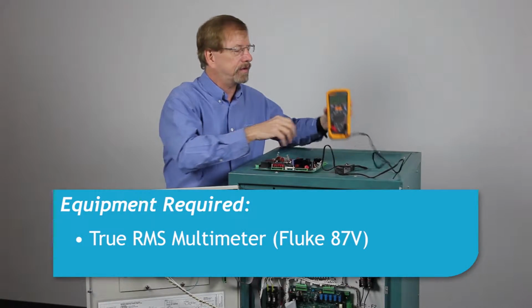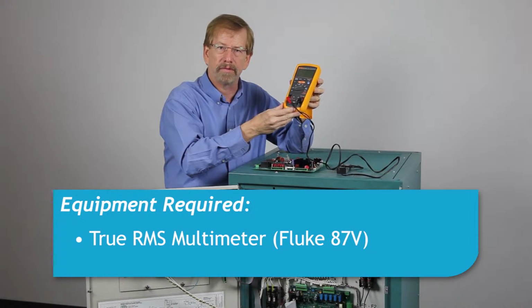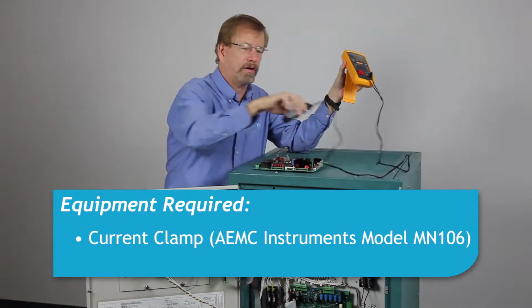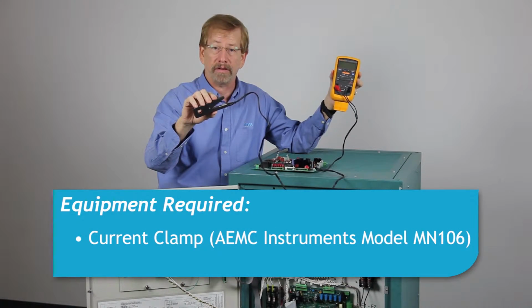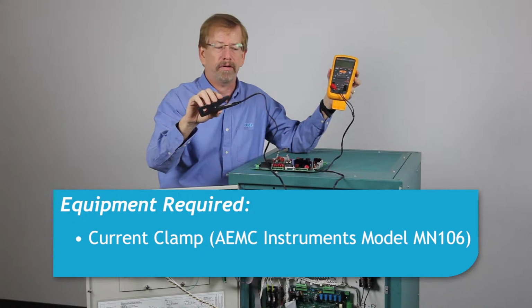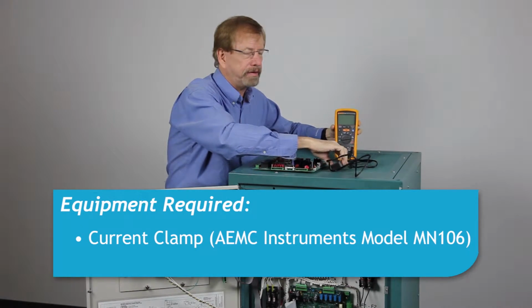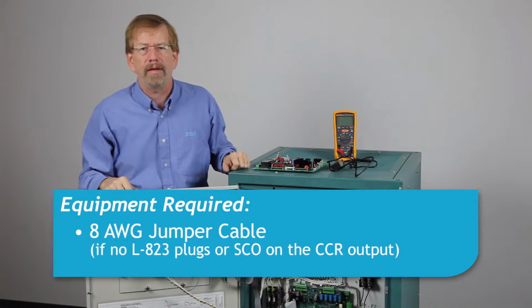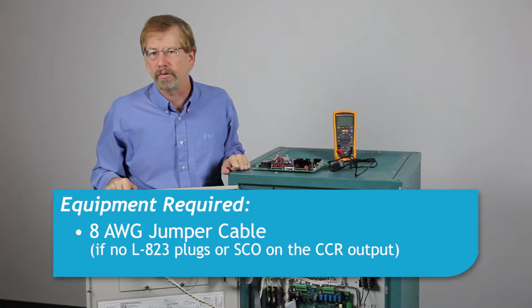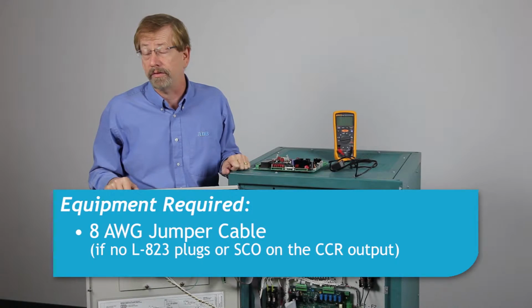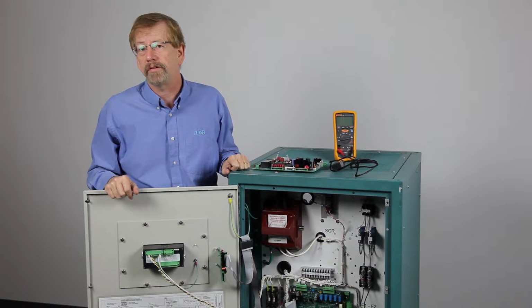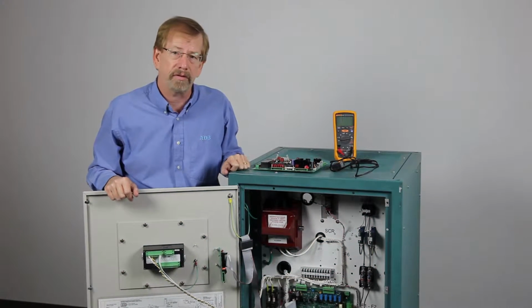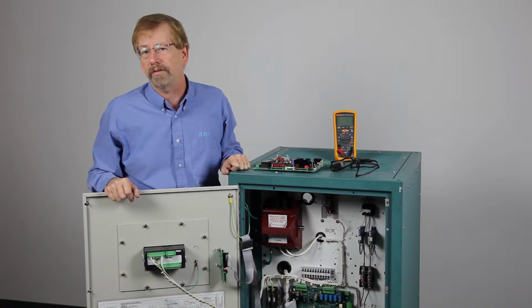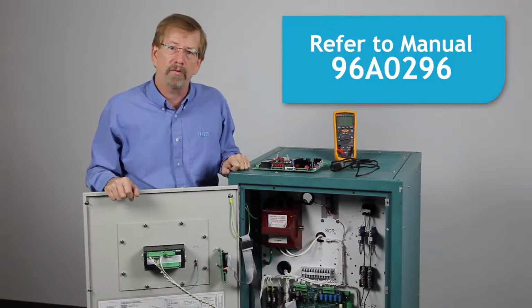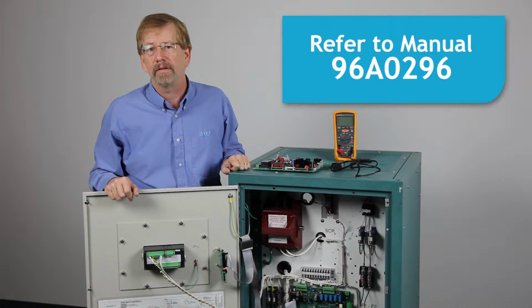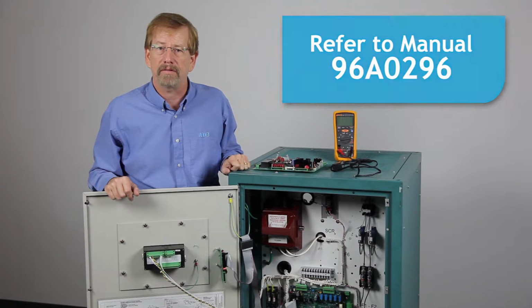First, you're going to need a true RMS multimeter with a current clamp in order to accurately get the output current measurement. Depending upon your installation, you may need an 8-gauge wire to short the output of the regulator, or alternately, you may use the series circuit cutout, which may be installed internal to the regulator or external to the regulator. You also will want manual 96A0296.